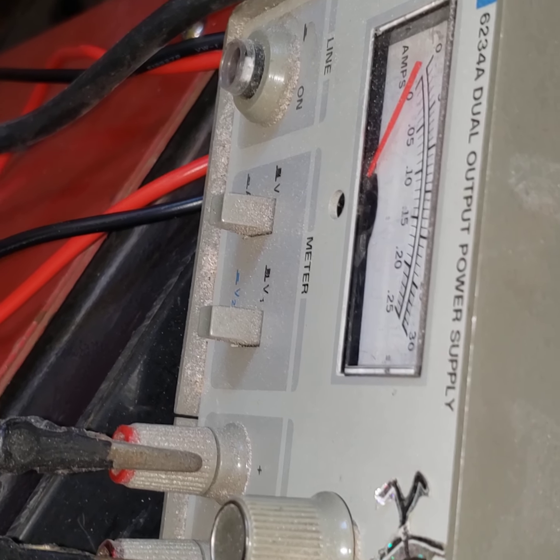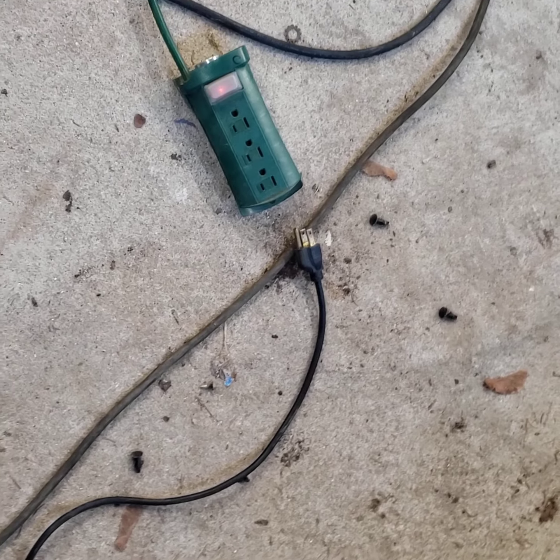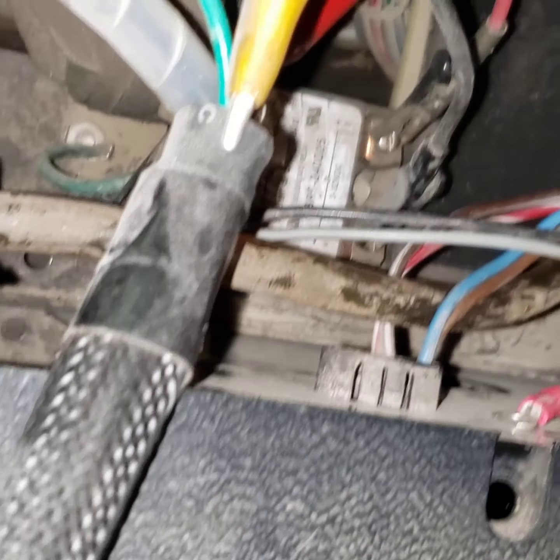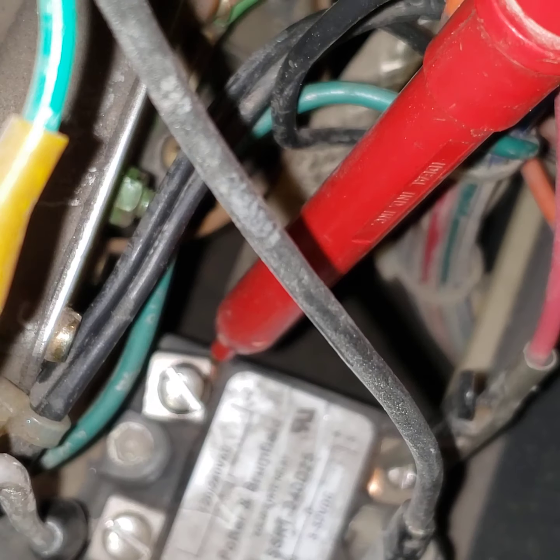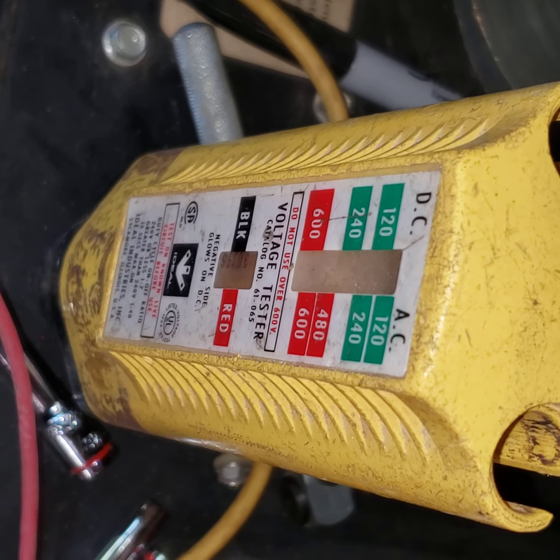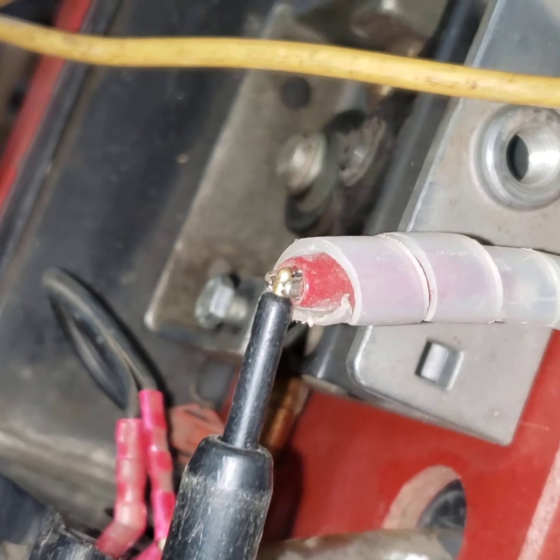Right now this is all off. I stayed within the 3 to 32 volt range and gave it 12 volts. I ran this cord out and plugged it in. I also have another thing here — basically an old cord with some clips on it; some people call that a widow maker. I have one clip on the load side of the SSR, and the other one's a probe to my Wiggy meter. You can't really test these with an ohm meter, as far as I know. The SSR output goes back to the neutral on the test lead.